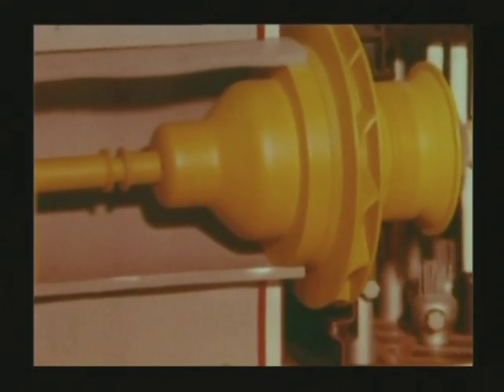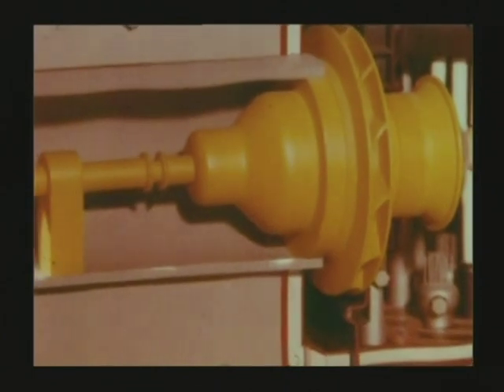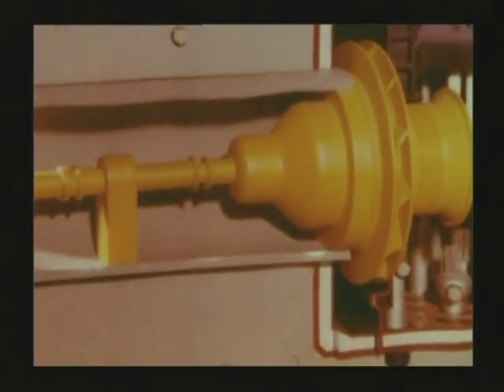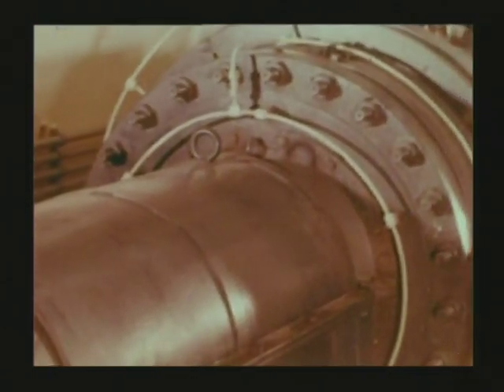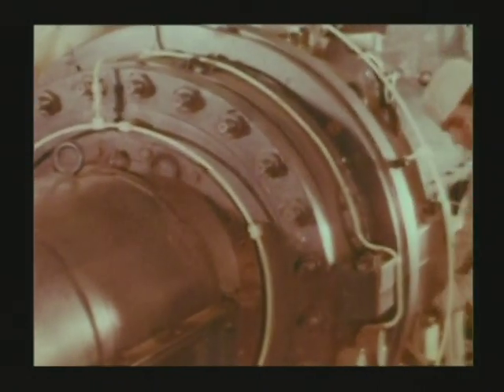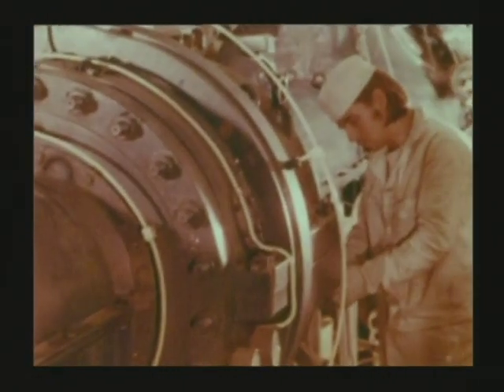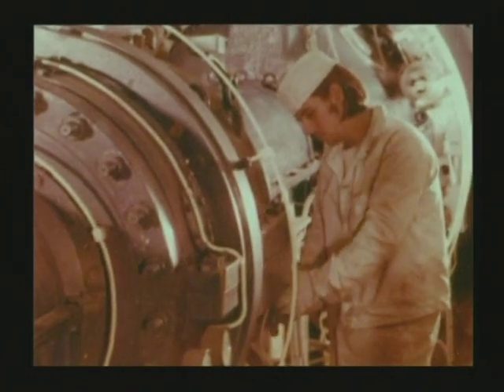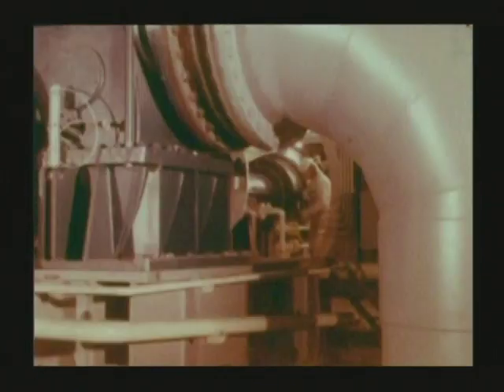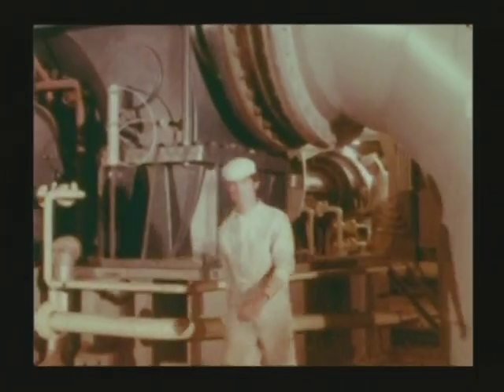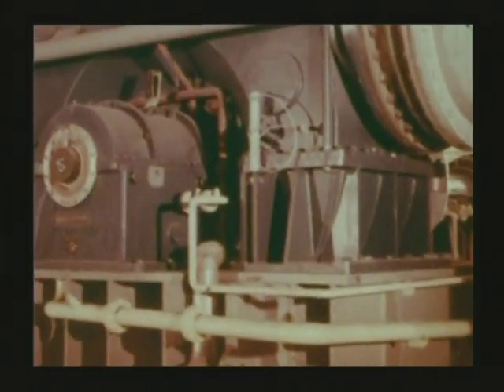The circulation of the heat-carrying gas from the bottom of the exchangers to the top of the stack is induced by 4 blowers. Tunnels are provided within the walls of the vessel to receive the drive shaft and the intermediate bearing. The blowers are driven by condensing turbines which receive their steam from the exchangers during normal reactor operation and from an auxiliary boiler during startup or standby service.